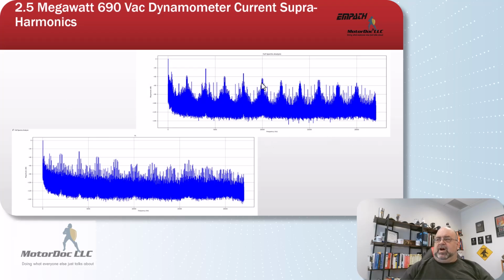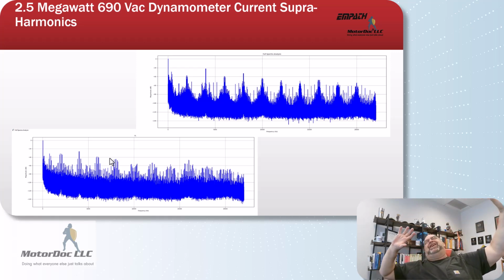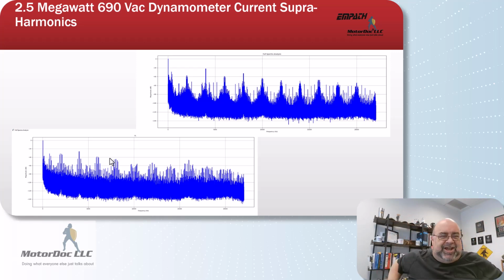This is on the power side from the system, from the drive to the machine, and then this was measured on the surface of the machine on ground. And when we took a look at it, now some companies refer to this as stray current losses. We're measuring the air gap of the magnetic field, stray fields from defect. Nonsense. They don't know what they're talking about. I am sorry. An electric motor's frame, and we've proven this time and time again, is a Faraday cage. All you're measuring is the leakage.